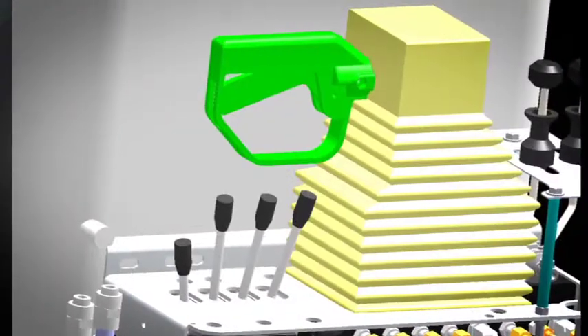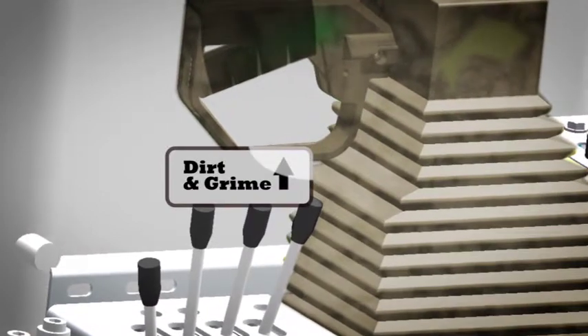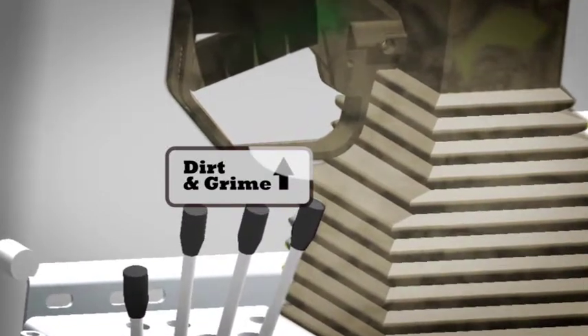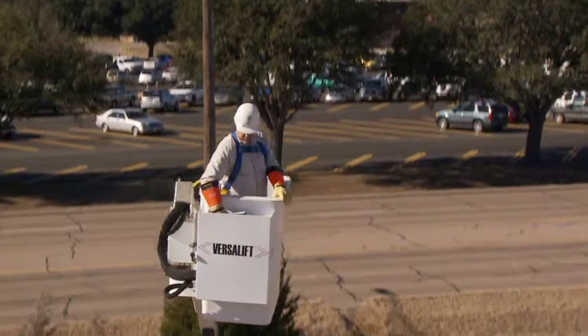We've all seen how upper control stations can become contaminated through environmental and contact contamination over the years of use. When plastic handles are new, they're tested per ANSI A92 dielectric standards and they will pass that test. The problems occur after they've been in the field for a year or two and owners are having an issue with them passing a dielectric test. And it's gotten so difficult that they'll actually deny they have these controls on there so they don't have to do annual tests on them.